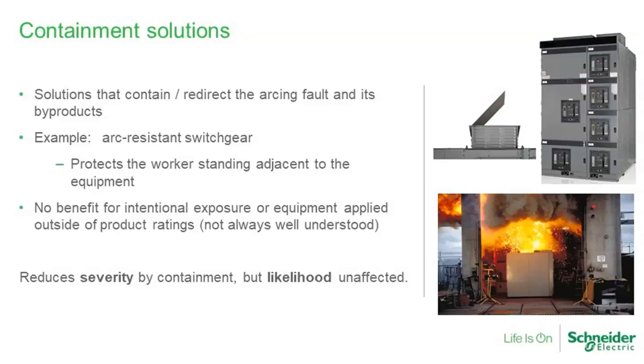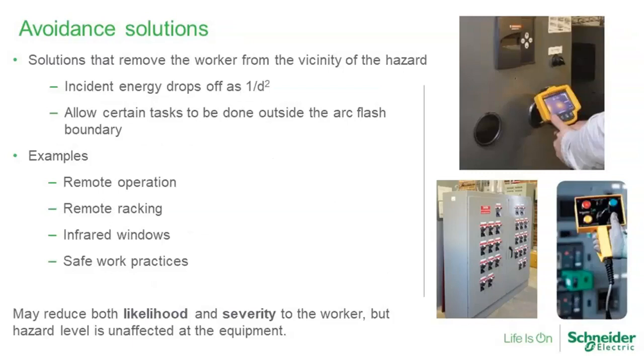One of the things it doesn't do is provide benefit for intentional exposures. What's an intentional exposure? Think of the cases where, for example, you're doing lockout tagout. You want to test to make sure voltage has been removed from this gear. What do you have to do in order to do that? You have to open a door or remove a cover on the equipment. As soon as you do that, the arc-resistant switchgear is not arc-resistant any longer. So we've bypassed the protection. If you want to use this, you really need to think about what kind of work tasks you're trying to protect your workers from, and make sure that those are compatible with the ratings and the intended operation of that gear.